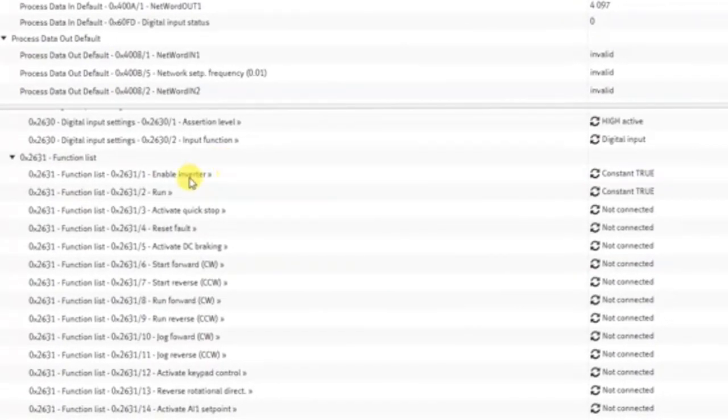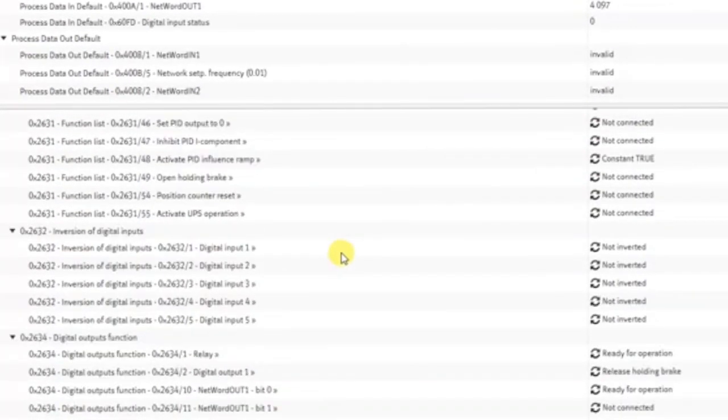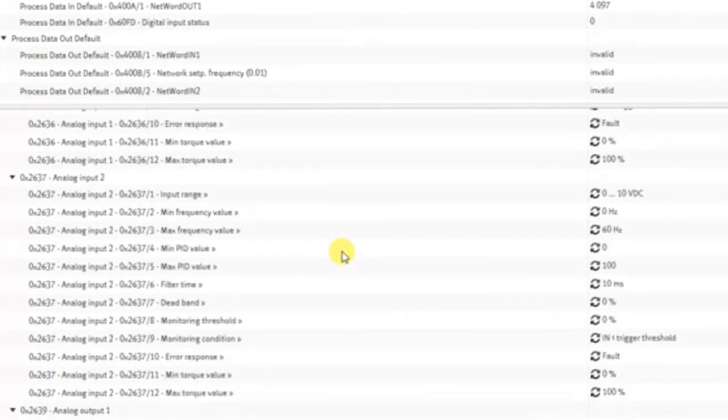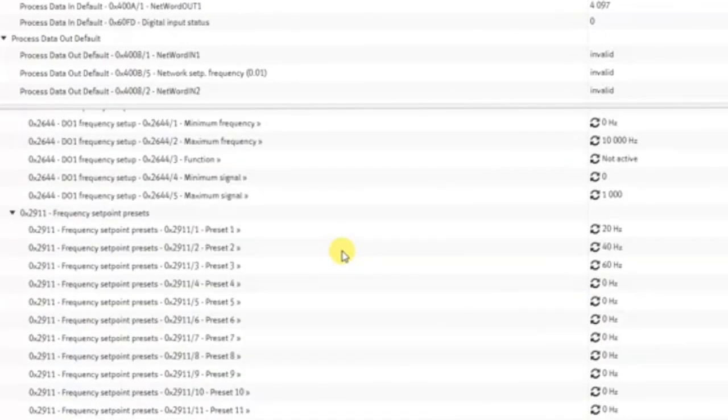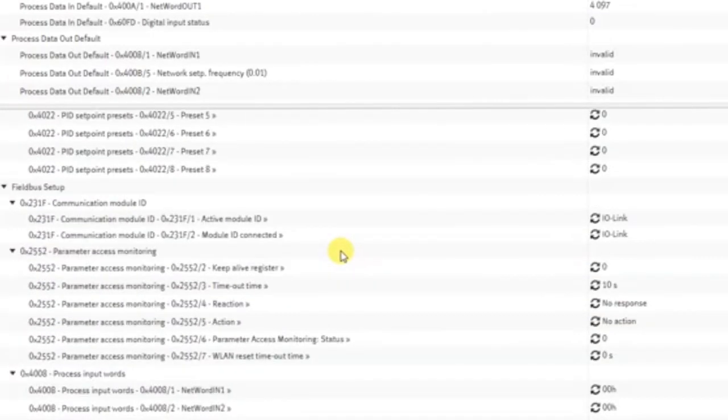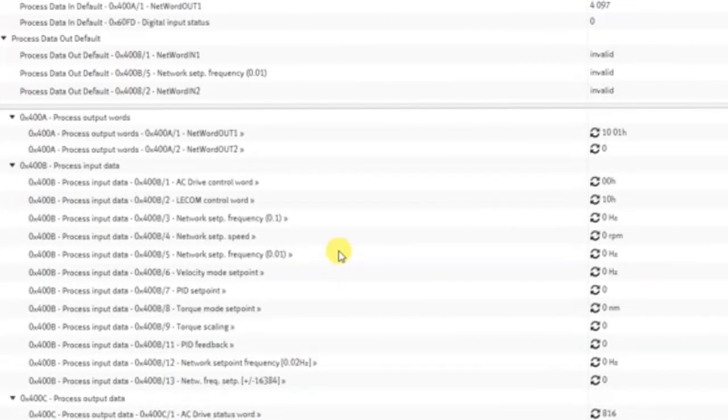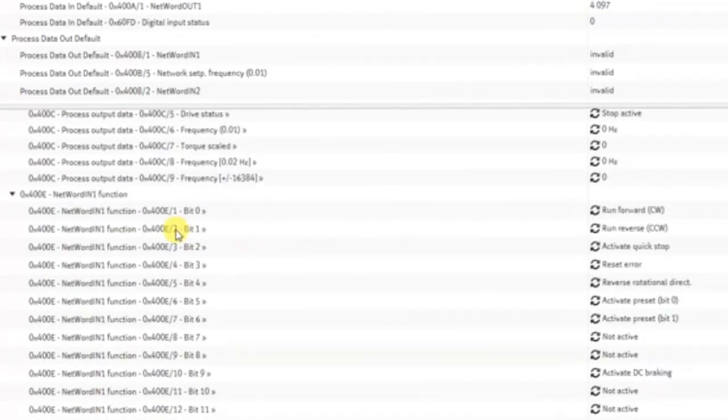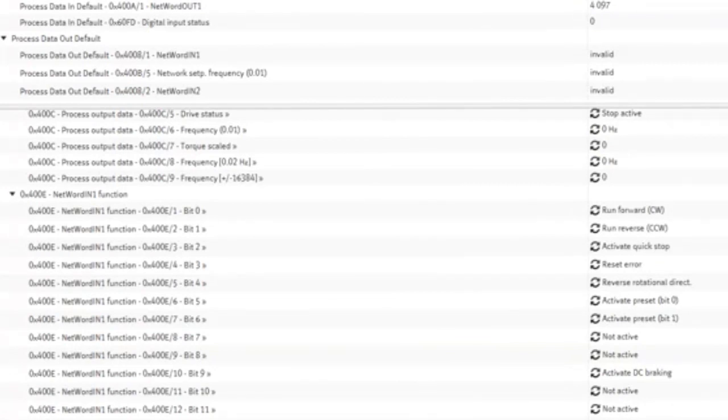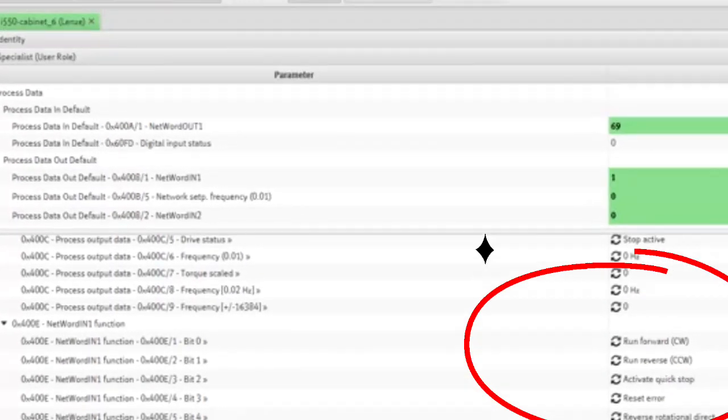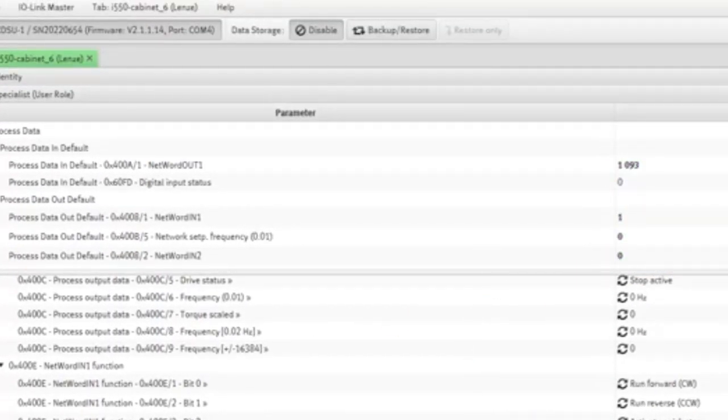So as you can see, I'm going to set the enable inverter and run bit to constant true. And then I'm going to scroll down through all of these parameters. I'm going to get down to where we set up the network word, which is our process out data. And then you can see off to the right hand side there, I've set like bit one is run forward, bit two is run reverse, quick stop.